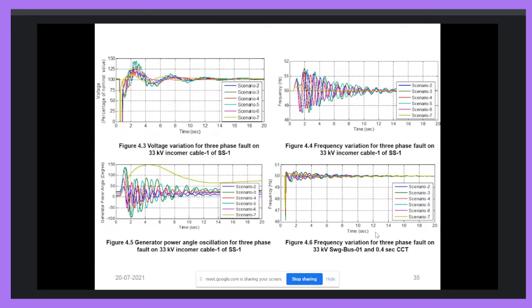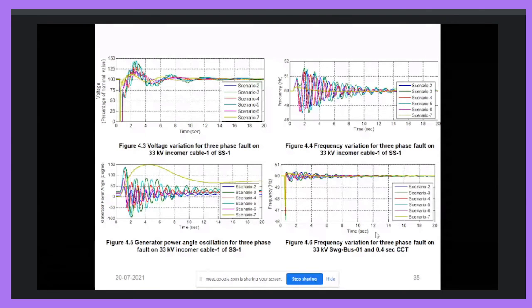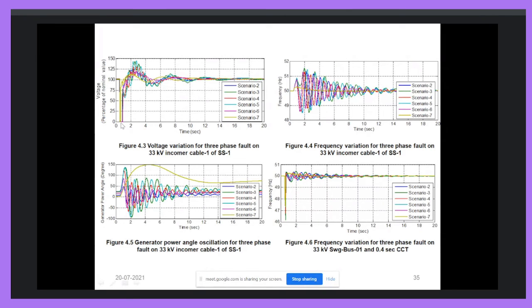Here you can see the voltage variation for the three-phase fault on the 33 kV incomer. 33 kV incomer means the supply which is coming from the utility. Whenever the fault occurred in a 33 kV system, we created the fault here. As you can see, the voltage is 0, and the fault is cleared by disconnecting the utility. So this is the voltage for the fault in a 33 kV system incomer. Here you can see the frequency. After clearing the fault, the frequency will be normal.